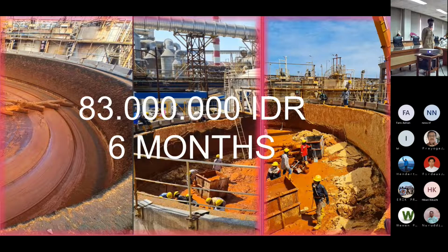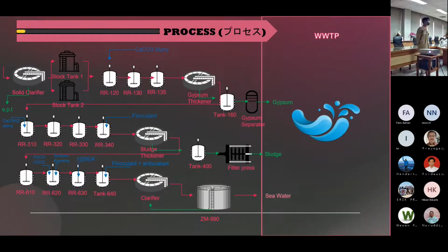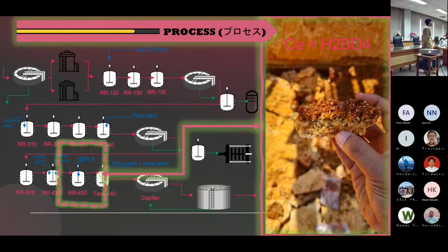And what is scaling? Scaling is mineral deposits of calcium ions that have precipitated out of the water. Calcium then combines with sulfuric acid in this tank. Sulfuric acid is added in this tank to decrease the pH because the pH here is very high.